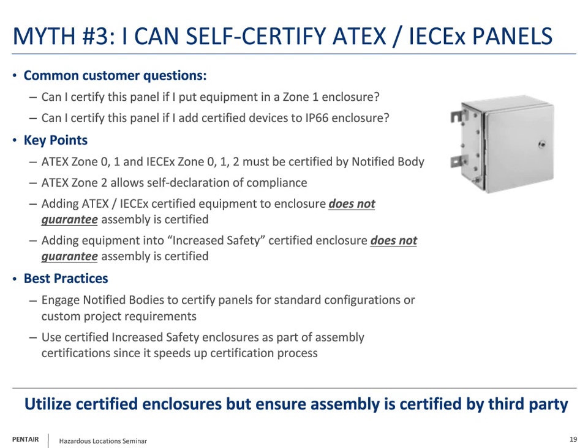So the point is adding ATEX or IECEx certified equipment to an enclosure doesn't really guarantee the assembly is certified, nor does adding general purpose equipment to a certified enclosure guarantee that the entire system is certified. Our best practice is to really engage with notified bodies to make sure that you're meeting the standard requirements, and use a certified enclosure as part of your system so that you can speed up the certification process. A lot of times, depending on your application, certifying bodies will look at the test profiles and say, well, we know the enclosure already passes all these different tests that are specifically for the enclosure, so you might only have to test the electrical system rather than just the enclosure. So just some advice on that.